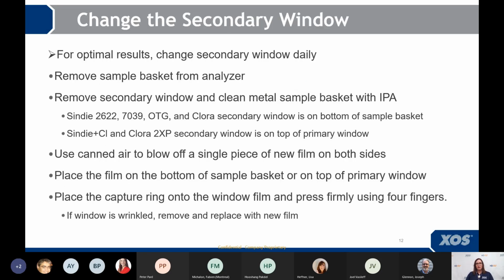Next, moving on to the secondary window. For best results, again, change it daily, or at least look at it daily, to ensure that it's not contaminated or wrinkled, okay? The first step to changing this is to remove the sample basket from the analyzer, and depending on your analyzer configuration, the secondary window will either be located on the bottom of the sample basket or on top of the primary window. When you're getting a new piece of film, we also recommend canned air here to blow off any contamination that may be on the film.